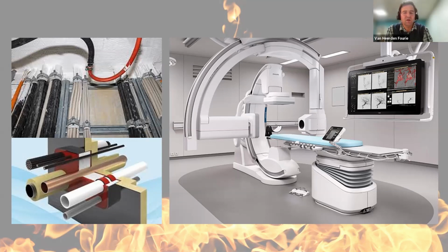If you think of the equipment we work with in a hospital, on your right is a picture of a biplane cath lab with penetrations through the slab for the high voltage cables to the tubes. If you need to replace those cables and you remove the fire stopping in that penetration, you are opening that unit up to risk should there be a fire in the area below the cath lab.